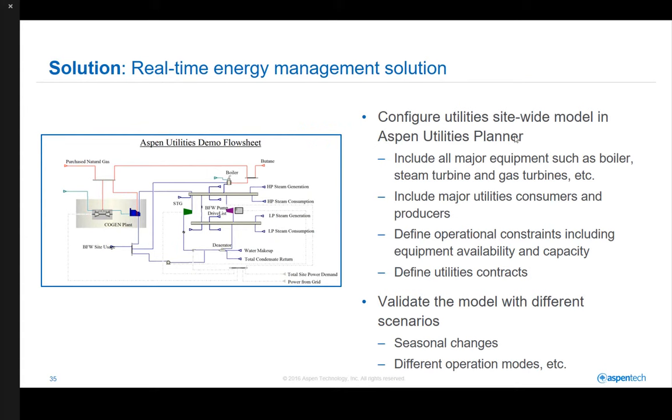Having these challenges in mind, a real-time energy management solution is proposed to help operators make better decisions. The deployment of the solution starts by configuring a site-wide utilities model in Aspen Utilities Planner. The model includes all major equipment such as boilers, steam turbine generators, and gas turbines. It includes all major utilities consumers and producers, and defines operational constraints such as equipment availability and capacity constraints. All utilities contracts are also fully defined in the model. Once the model is configured, it must be validated with the plant data for different operating scenarios, such as seasonal changes and different operation modes in the production processes.